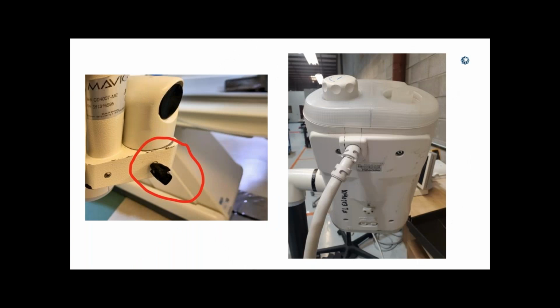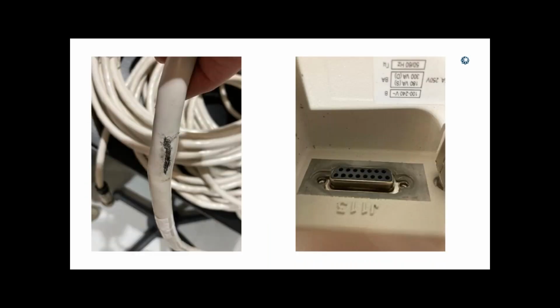So this is some of the things that we have found when these things get sent in to us. They don't want to do the PM themselves, so they send them in to us to do the PM. Broken knob, damaged head cable, cut cable, standoffs on the actual cable connector missing. And they wonder why they get intermittent errors.